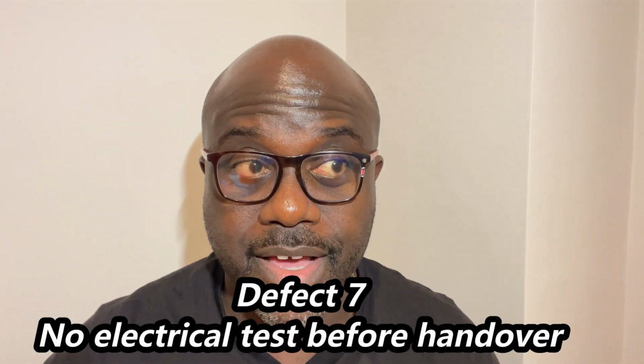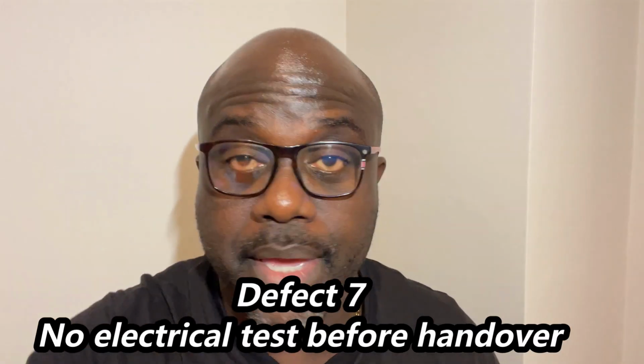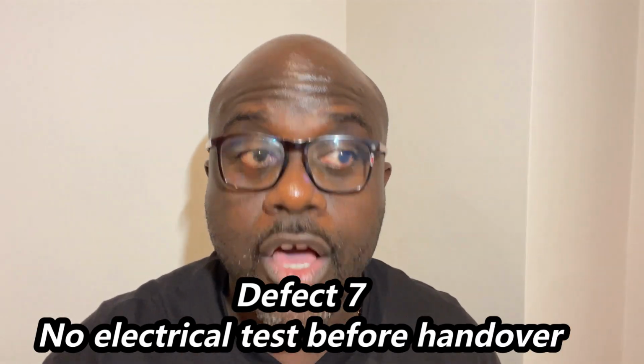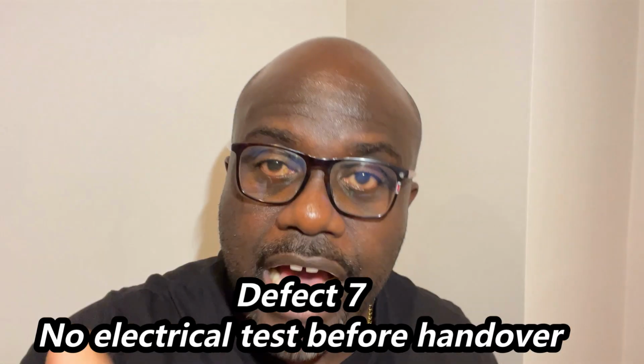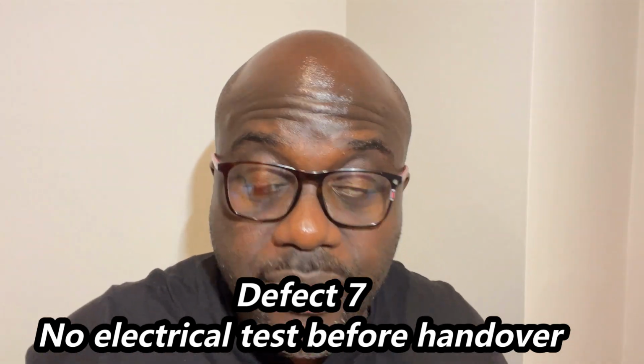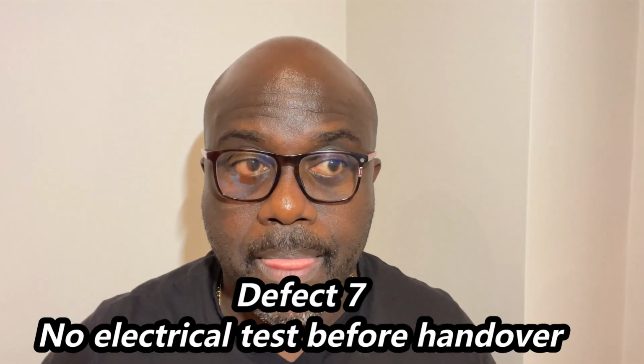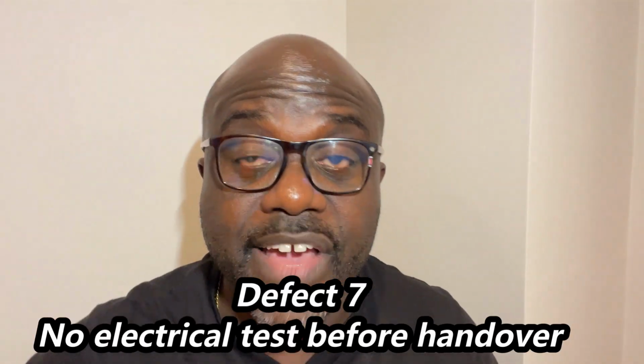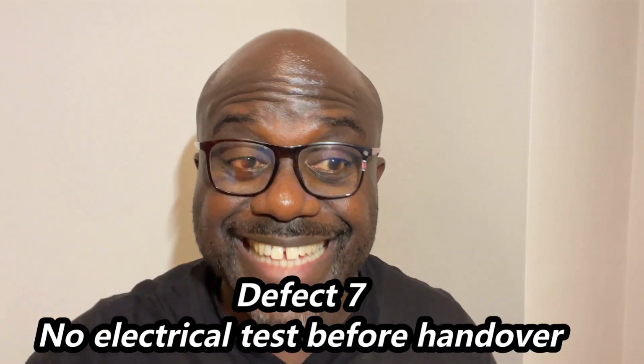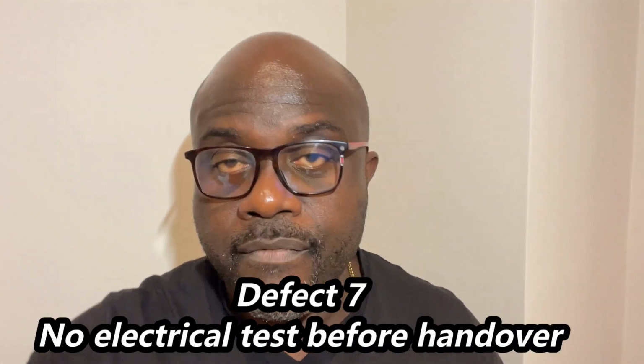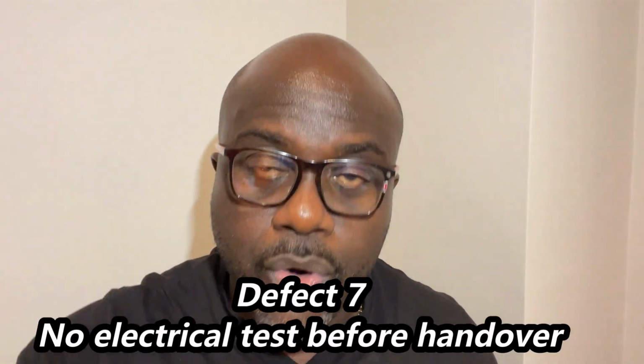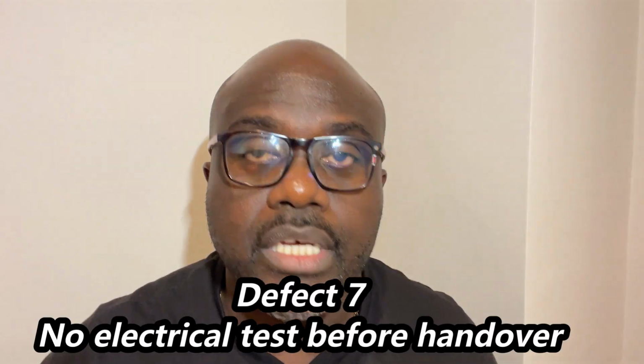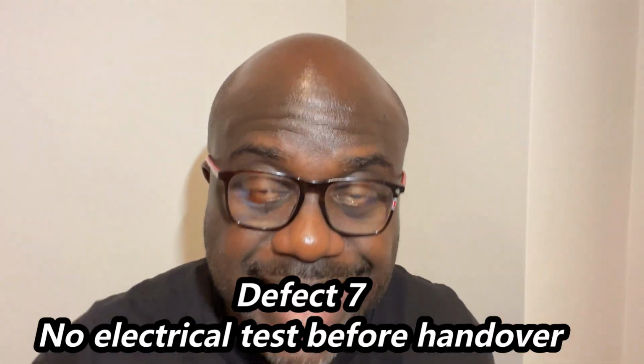Defect number 7. No electrical testing before handover. This is a big, and I'm going to call it a systemic failure. Many homes are handed over without electrical insulation resistance testing, without RCD trip time verification, or even operational tests, without earth resistance tests, earth loop impedance tests. Without testing, defects remain unknown until failure. Electrical testing isn't just paperwork, it is fire prevention. For buildings in Ghana, ensure that you push for the Energy Commission to come and do the electrical testing before the building is handed over, to give you that peace of mind.